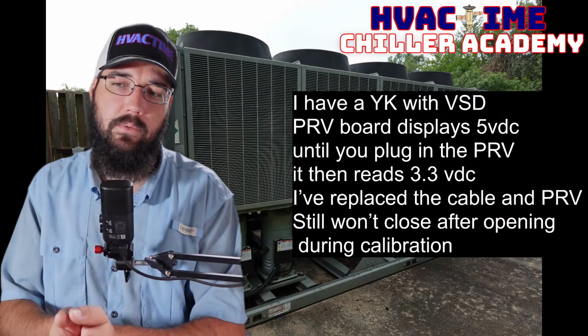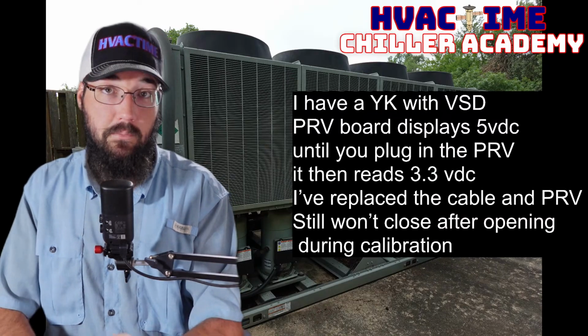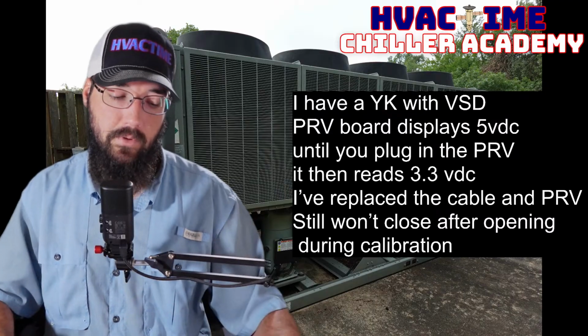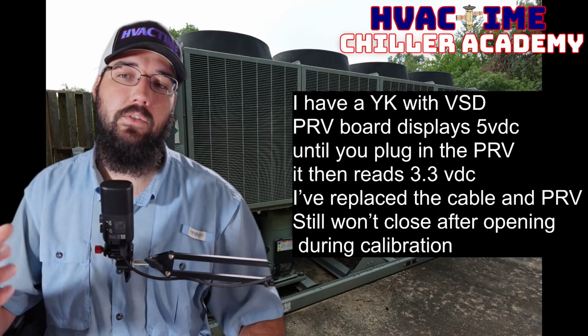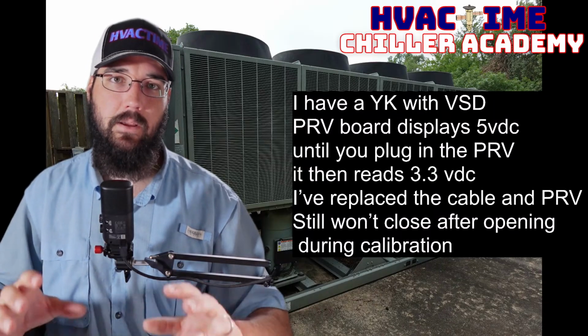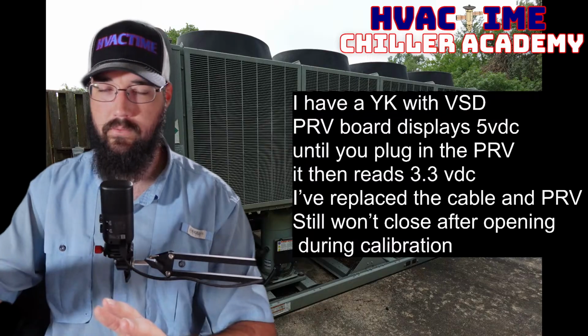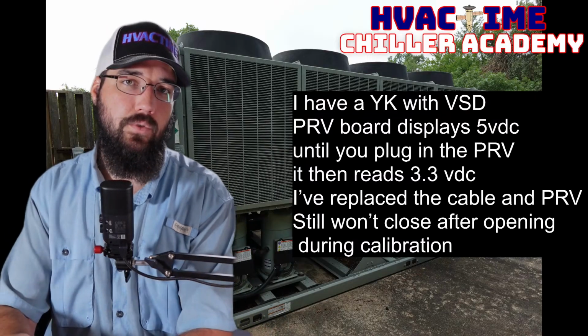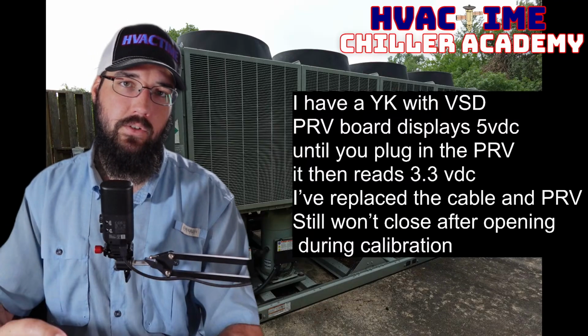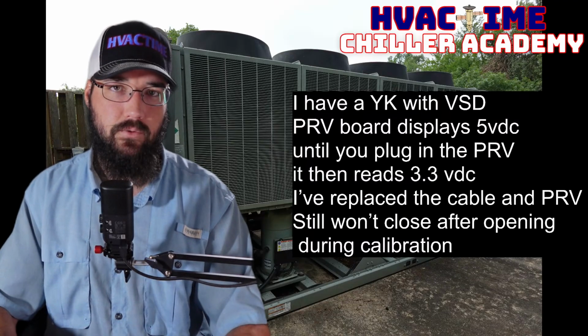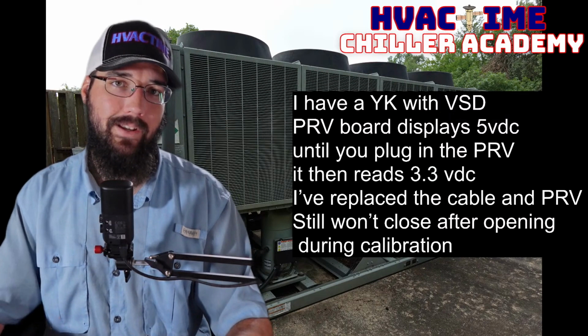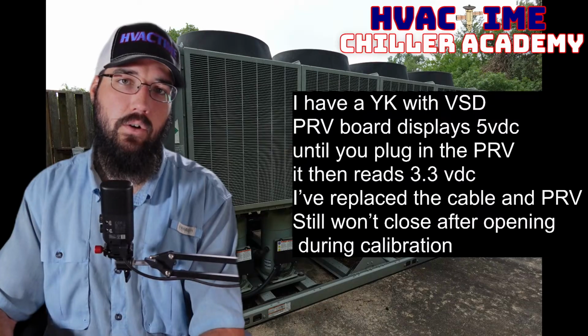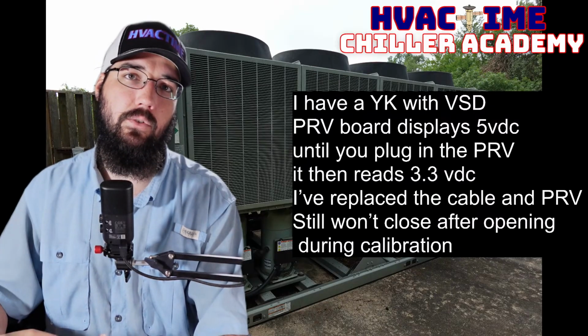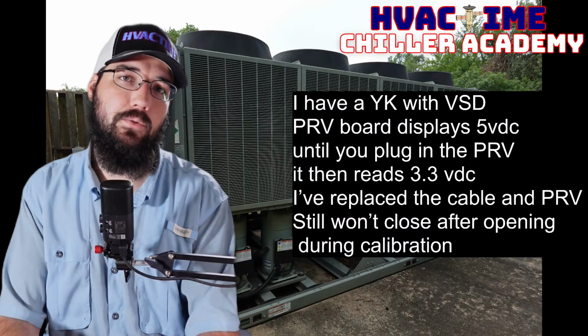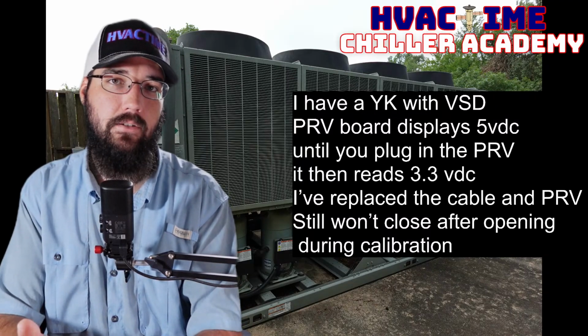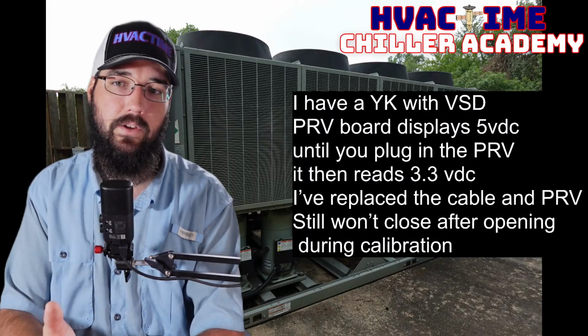Either way, you replaced the cable, replaced the PRV, and it still won't close. So either way, the module itself or the wiring, those would be the two main things I would be worried about. Without a load connected, a module or a board may show full voltage output and show that just fine. But there could still be weak components inside of the module, so that once you plug the component into it and put a load on it, because of the load, the weak circuitry internally is not able to properly supply that component, whatever the component is, in your case a PRV actuator.